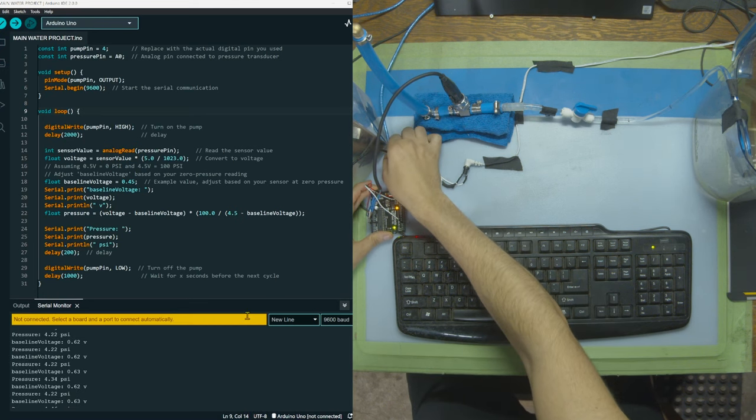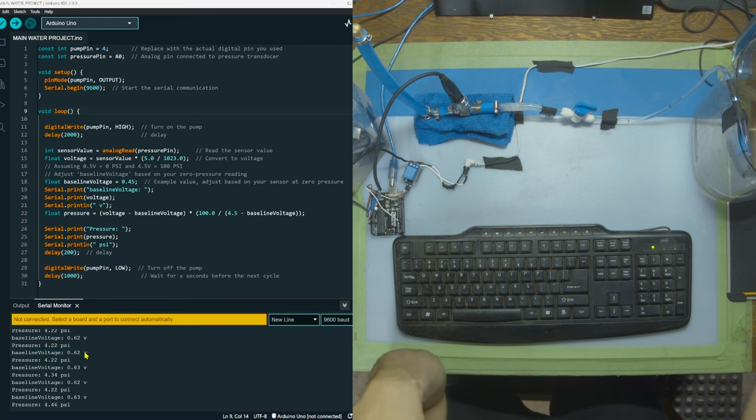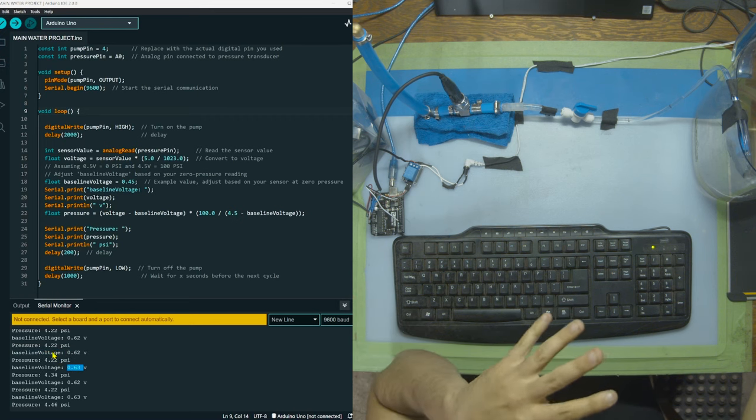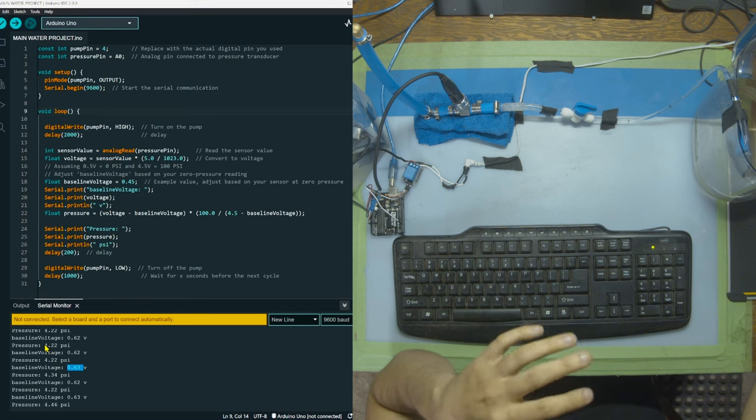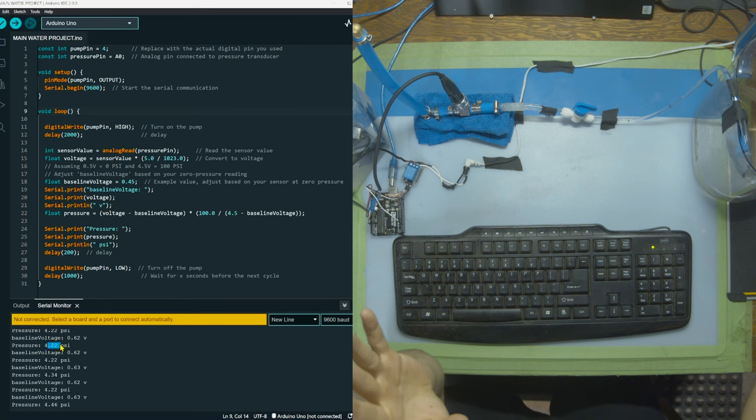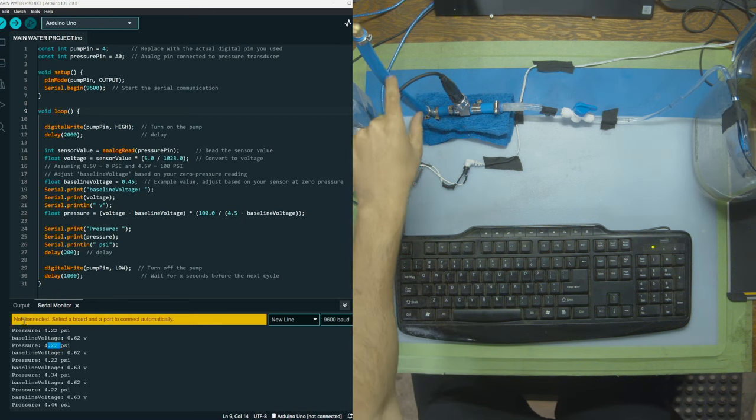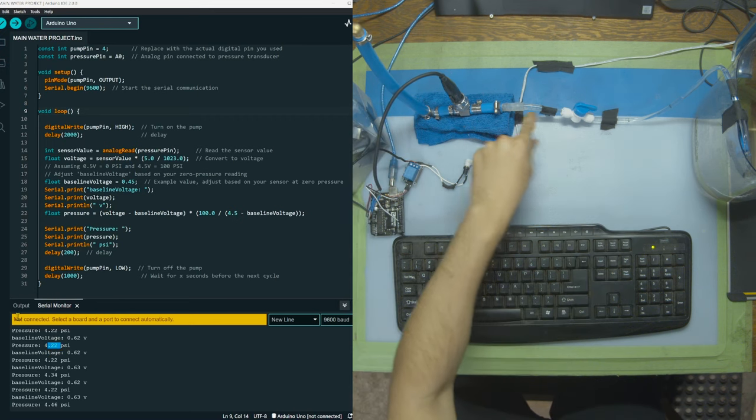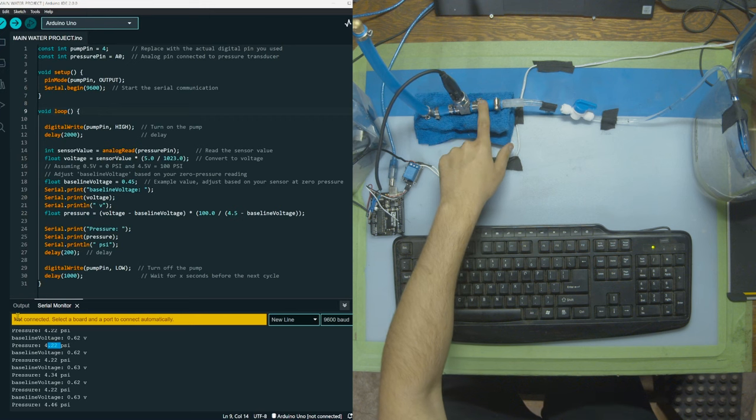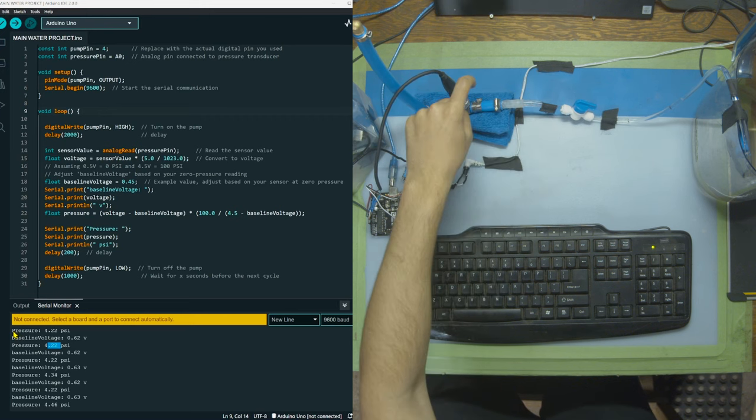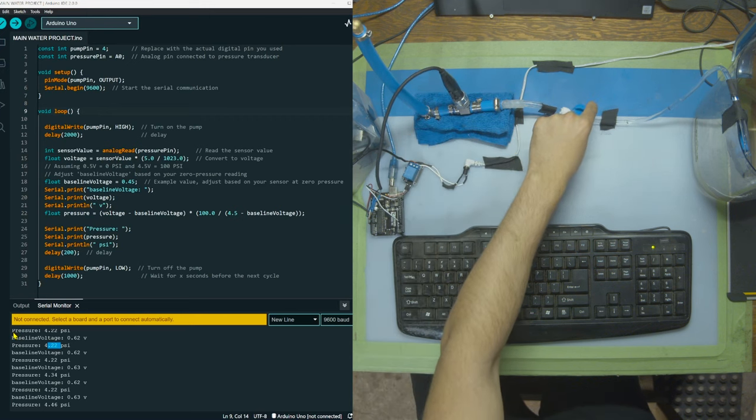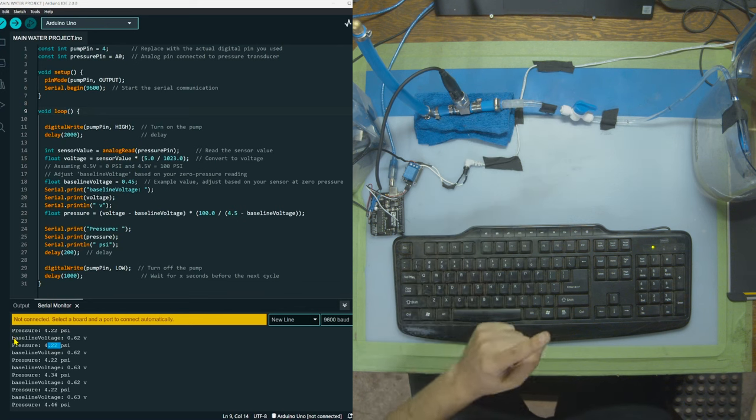So now we're getting more voltage because we're getting more pressure and through that we can calculate what pressure we're currently at. We were at 0.1 base, maybe 0.2 and now we're at 4 psi. So the pump on, tubing all open just with a reducer here going from big pipe to small pipe, just with that we're getting 4 psi. Now let's close this and see what number we're getting.